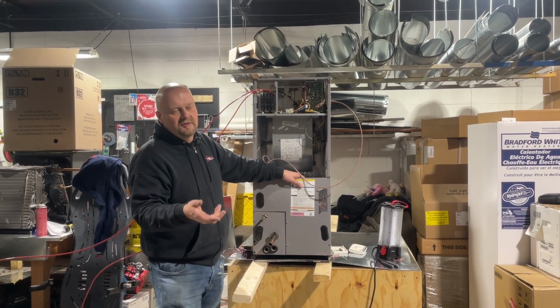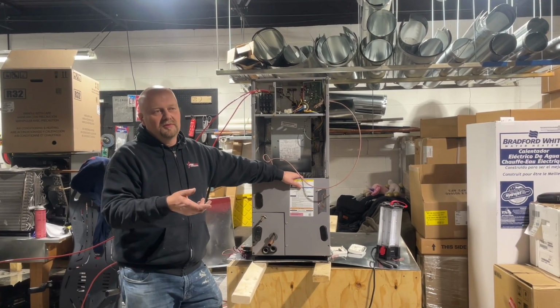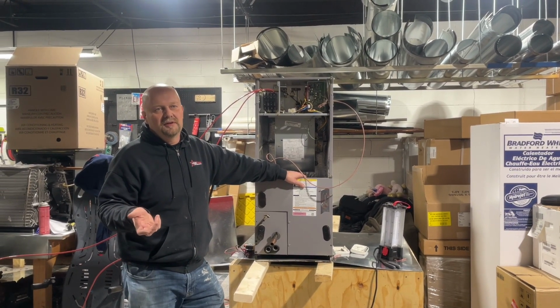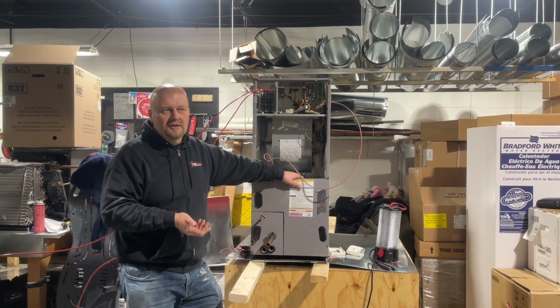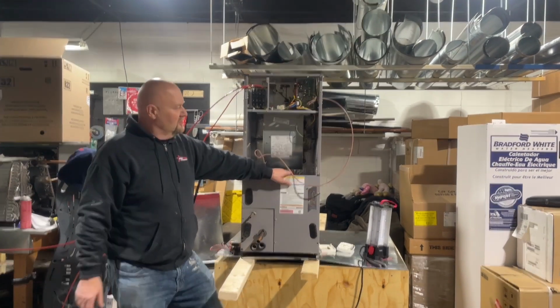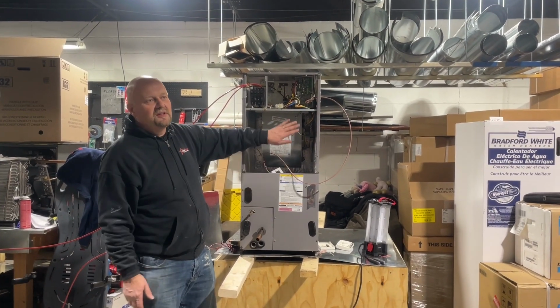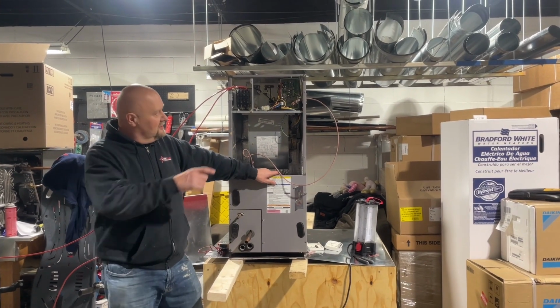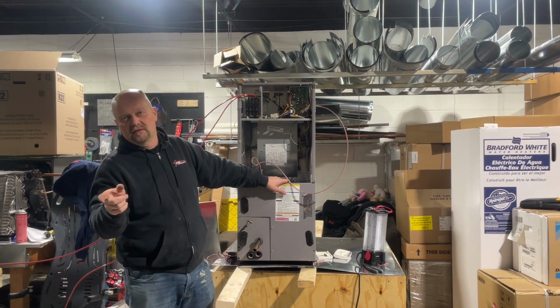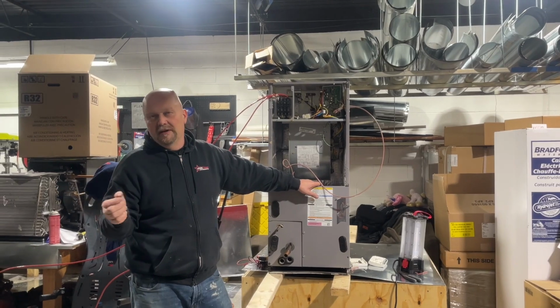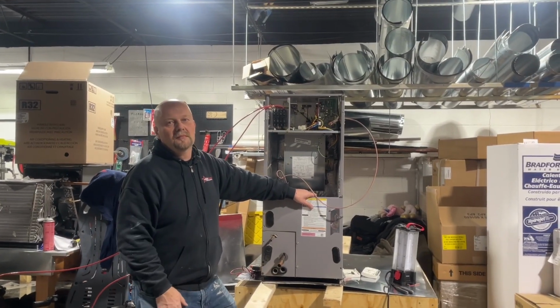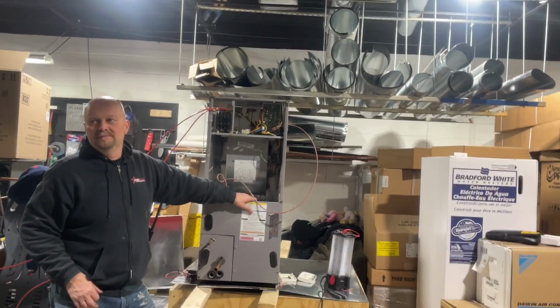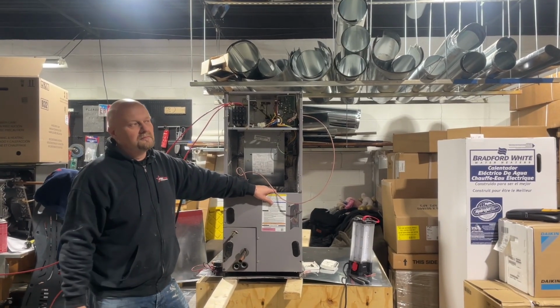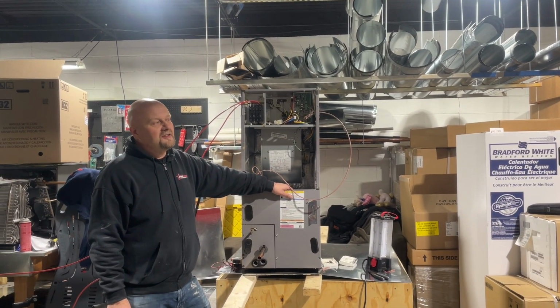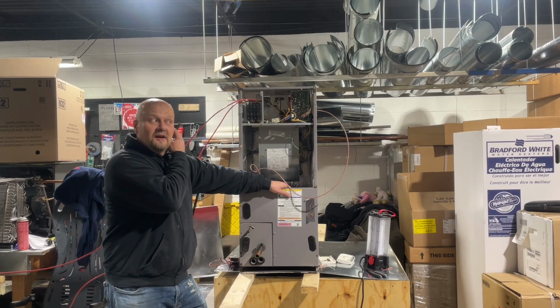Like Unico systems, some of the bigger ones go up to 25 kW, but you can go as low as 5. Yeah, they range from 5 to 20 on non-standard air handlers. So don't try to read it from the model number of the equipment, unless someone wrote it, unless it's factory installed. They will denote on the data plate, if it is, there'll be an X next to the kilowatt electric heat kit that is installed.